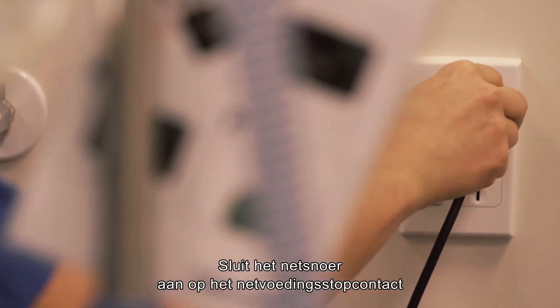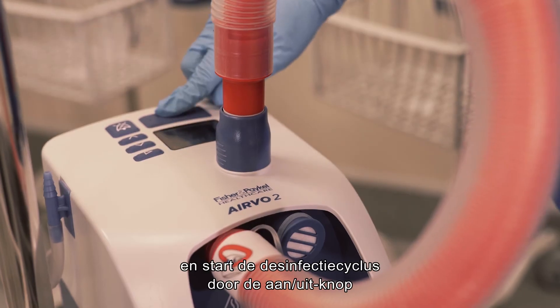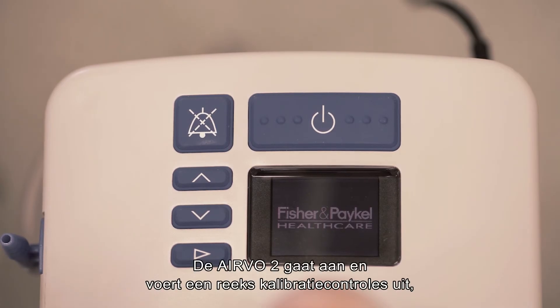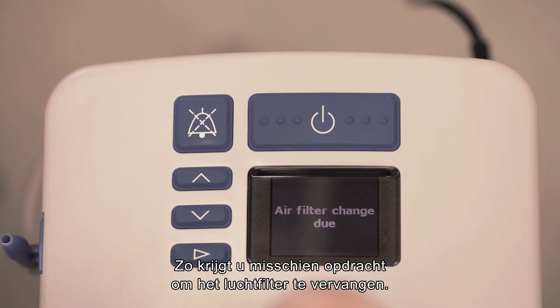Connect the power cable to the mains utility power socket and start the disinfection cycle by holding the on-off button for three seconds until the unit beeps. The AIRVO 2 will turn on and run a series of calibration checks, raising an alarm if any problems are detected. For example, you may be prompted to change the air filter.